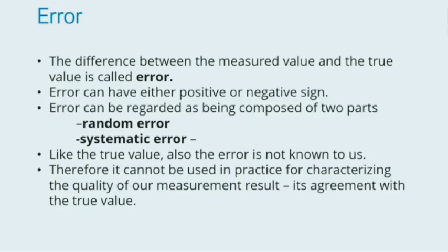A systematic error is an error which you cannot change because it is so strongly associated with the system. For example, if you have set the oven at 100 degrees, however it reads 105, then that 5 degrees is an error. This is a systematic error which will be carried over to any analysis you do using that oven. The only way we can rectify that error is to calibrate or recalibrate the equipment, or check whether some sort of electrical or electronic problem is there. So it is systematic unless we have rectified it. Irrespective, it just continues along the line.